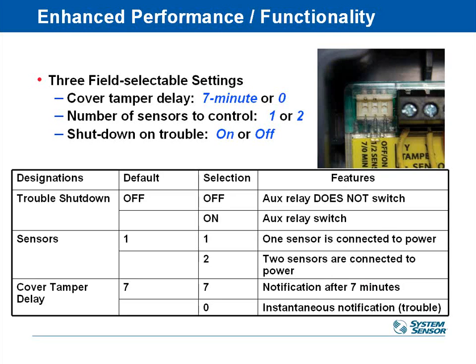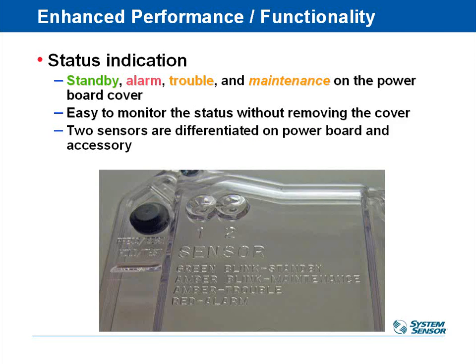Sometimes inspectors don't like that. I mean, it's nice because it avoids nuisance alarms if someone's working on the system, but sometimes inspectors don't like that, and if the cover comes off, they want it to immediately alarm, so you can go ahead and change that to 0 minutes.